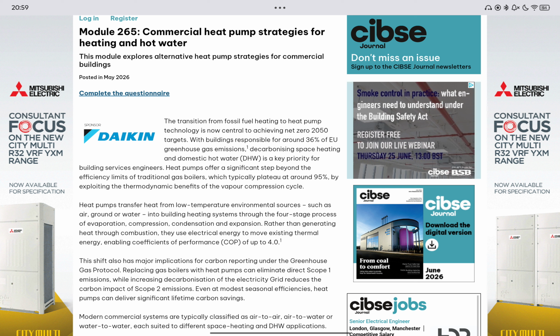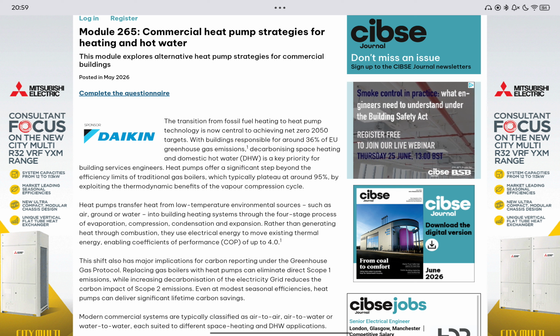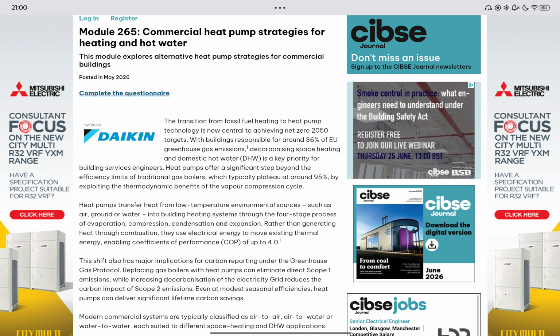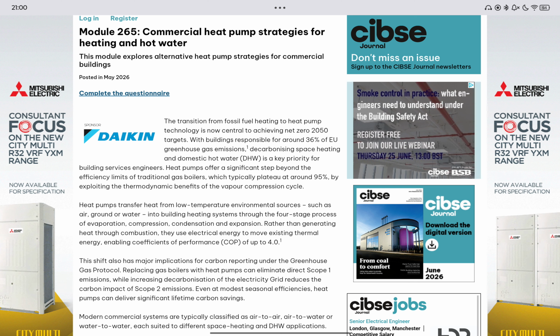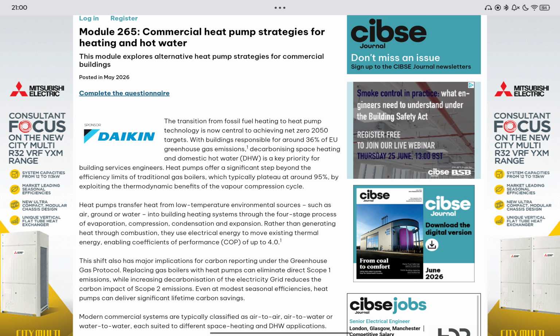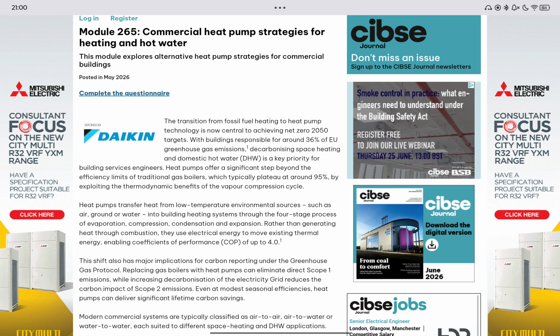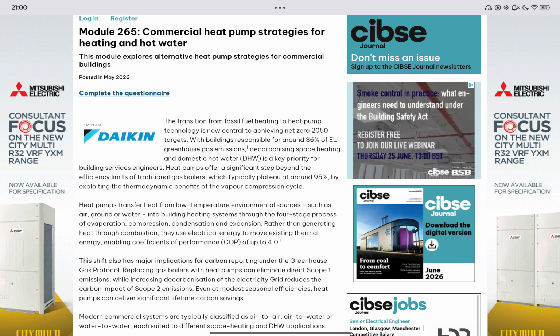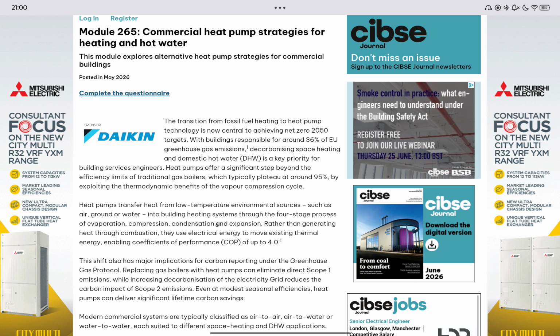The transition from fossil fuel heating to heat pump technology is now central to achieving net zero 2050 targets. With buildings responsible for around 36% of EU greenhouse gas emissions, decarbonising space heating and domestic hot water, or DHW, is a key priority for building services engineers. Heat pumps offer a significant step beyond the efficiency limits of traditional gas boilers, which typically plateau around 95%, by exploiting the thermodynamic benefits of the vapour compression cycle.